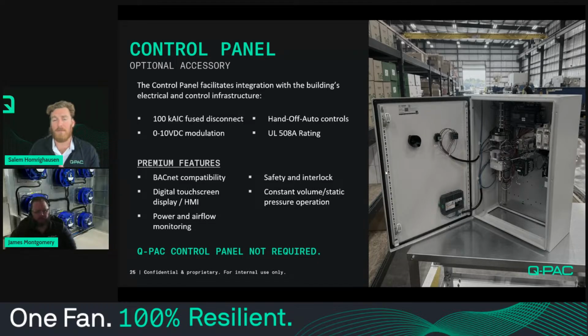Usually you can hook up a static pressure sensor two-thirds of the way down the duct, and that's going to go back to the control panel, and you can then program the HMI to tell the PLC to maintain that static pressure. So it's a pretty cool feature, and it's great for those folks, again, that don't have the more sophisticated BMS. It's going to come standard with a fuse disconnect, and it's going to have all the electrical power infrastructure inside of it to manage that for your fan.